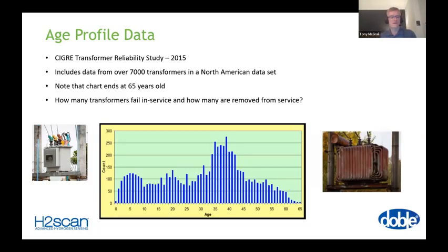What we do know is the age. Now, things, as far as I know, don't fail just because of their age. They fail because there are failure modes which exhibit themselves over time, and that time is going to be the age of the unit. For example, the number of through faults that we see on a transformer will increase, not because the transformer is old, but because it's old and is in a particular area. The degradation of paper, which is a one-way process, will result from temperature, from oxygen, from moisture. Those three things will act upon the paper over time. So the time by itself needs something to make the transformer deteriorate, and we call it aging, even though the age itself is not an indicator of whether the transformer is in good or bad condition.